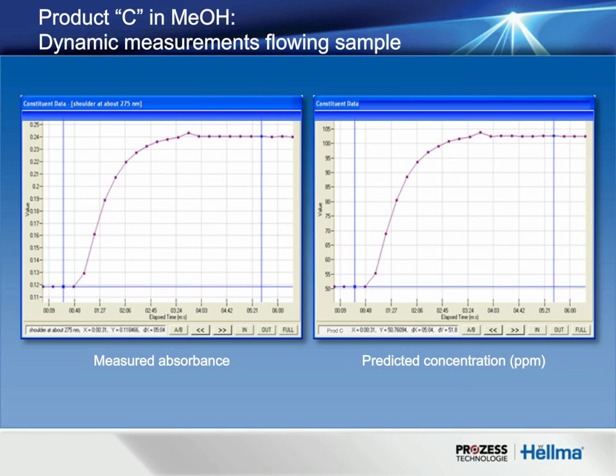Okay. This averaging method can also be used to accommodate processes where you have bubbles in the process itself or in the effluent during the cleaning process. The bubbles will only be in the light path of the probe for a brief period of time, and by averaging, you can essentially eliminate the aberrant data from the overall results. Okay.